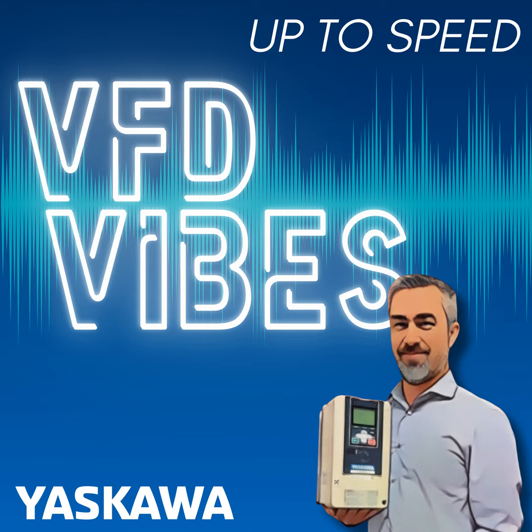Efficiency is so important, both in terms of environmental and financial impact. If I remember my affinity laws correctly, in a V/F application, such as a fan or pump, when we lower our speed by 50%, we actually reduce our energy consumption in the area of 80 to 90%, and that's a pretty darn big reduction. Now, being a Yaskawa tool, I'm assuming all or most of our drives are in the software, and you simply select the one you want to evaluate in your application. Is that correct? That's correct. The energy saving predictor lets you put in the motor information.